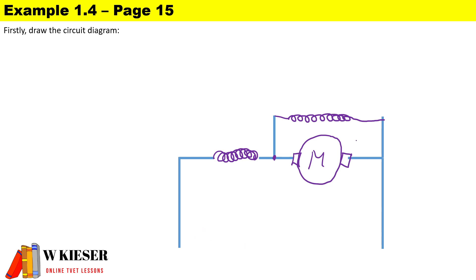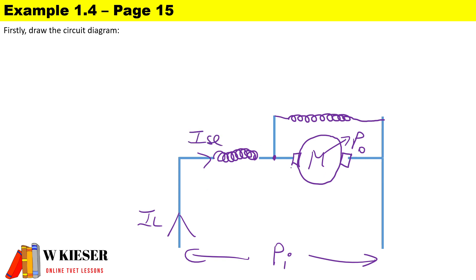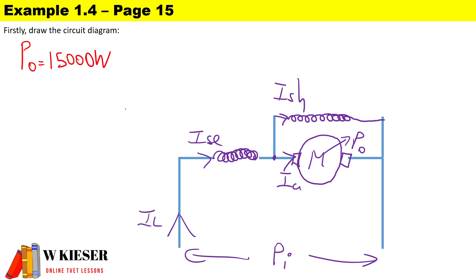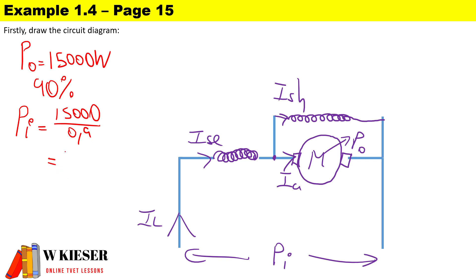This is a motor — mechanical output, electrical input — with terminal voltage across the terminals. The supply current passes through the series winding; most current goes through the armature and a small amount through the shunt winding. The output power is 15,000 watts. To calculate input power: 15,000 divided by efficiency of 0.9, giving an input power of 16,667 watts.